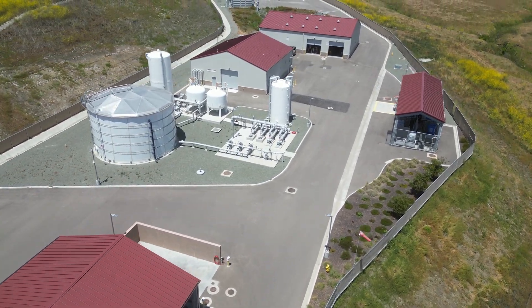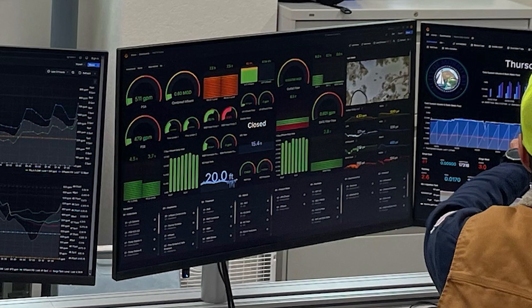We started using Grafana in 2019. The old wastewater treatment plant, which was built in 1960, had two metrics that were most important. My lead worker at the time told me he used to be able to pull it into a browser, but that piece of equipment was 20-plus years old — it was just a snapshot of a really bad graph. I told him, give me a couple weeks and I'll figure out how we can record this better. I utilized Python and an industrial library for Modbus TCP, pulled that data into InfluxDB, and then I needed a place to see it. Grafana turned out to be the answer. We had our two metrics beautifully visualized in Grafana, and that was our first exposure to it.